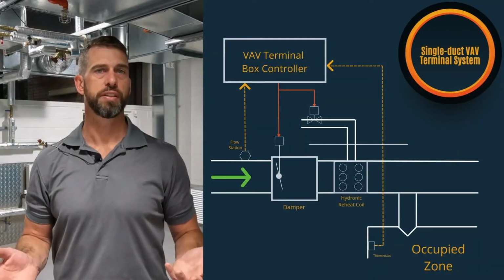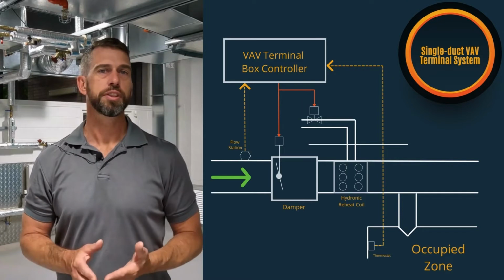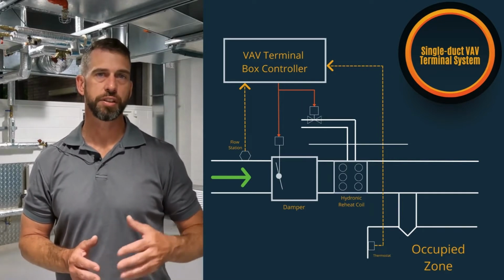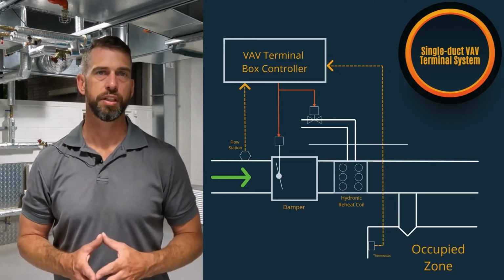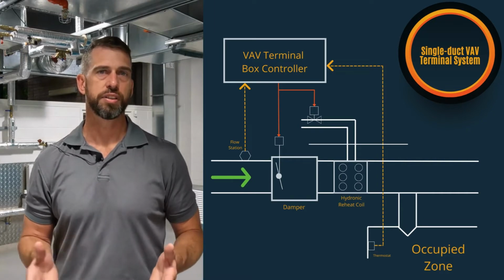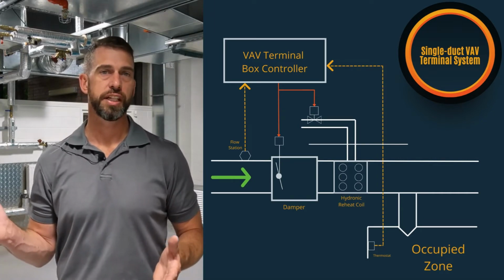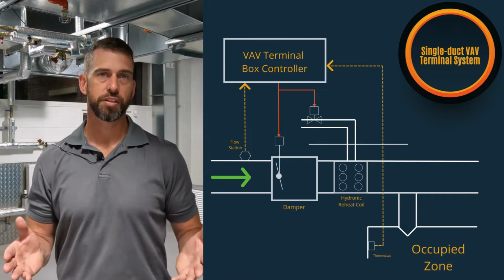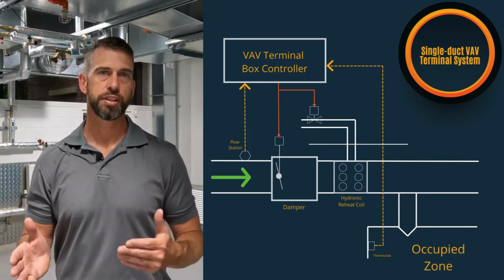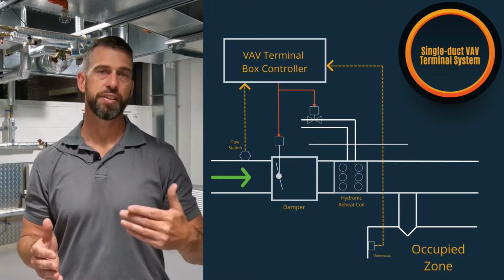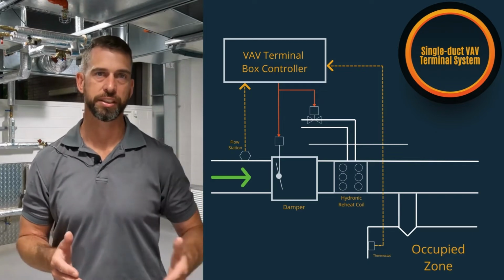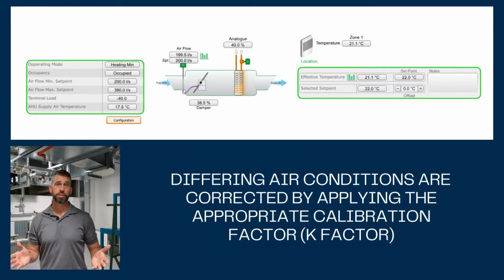So why do we calibrate the VAV box? Systems are designed to have a specific amount of air delivered to a particular part of the building. In the case of a VAV box, an air handling unit delivers air down the primary duct. It's measured via a pitot tube at the inlets of the VAV box. The VAV box actuator then controls the air to the occupied space. Every VAV box has slightly different entering air conditions, and the K factor or calibration factor of that particular VAV box accounts for those differing entering conditions.